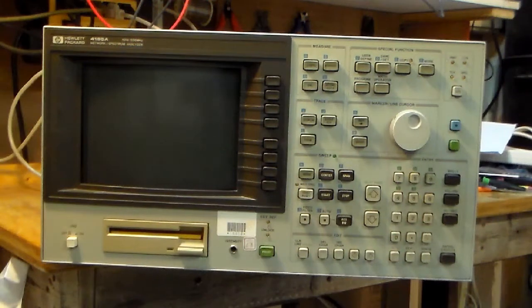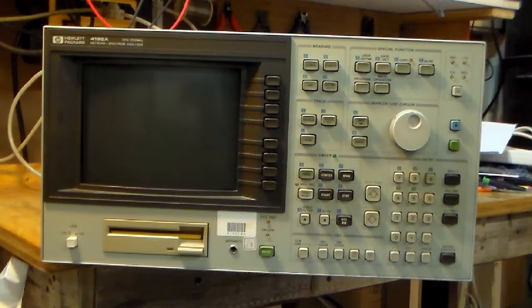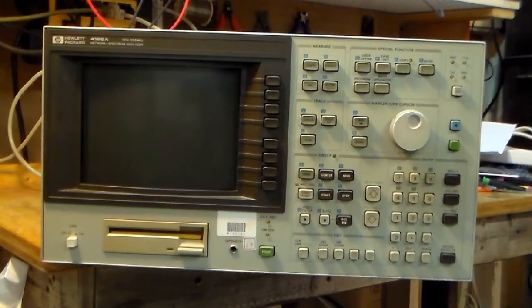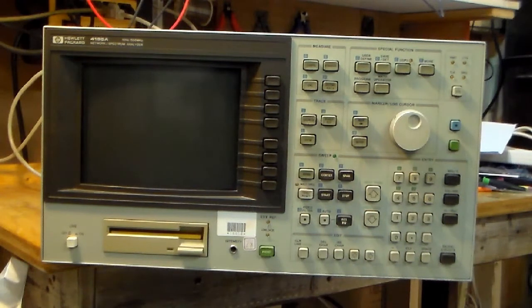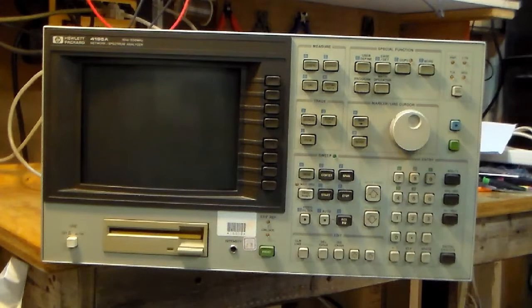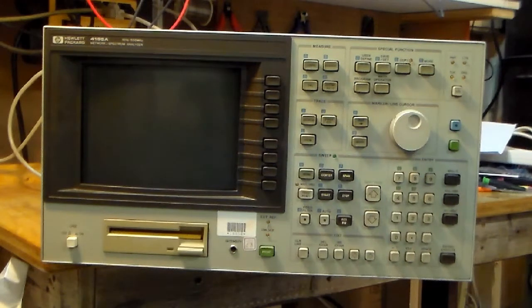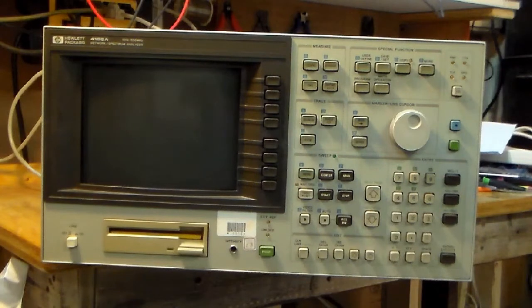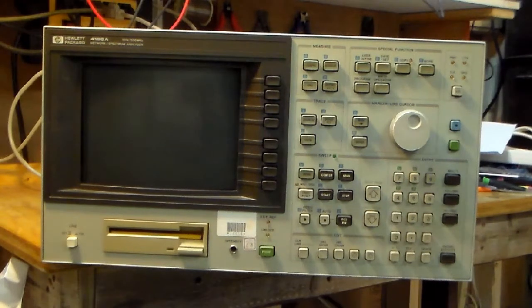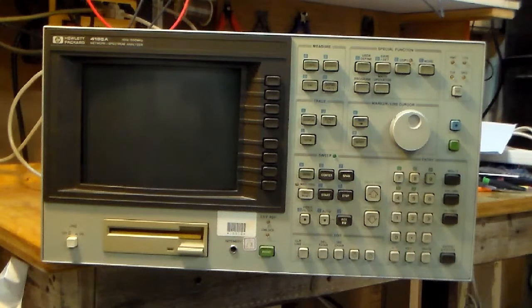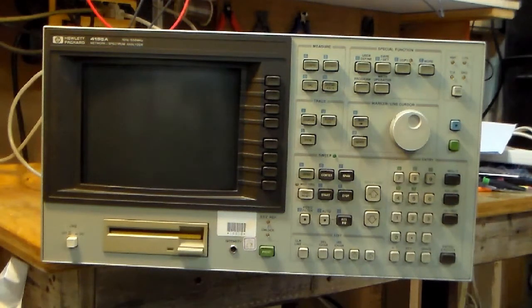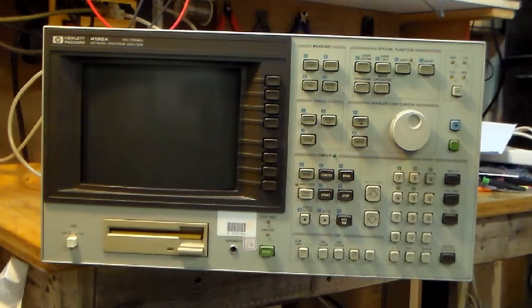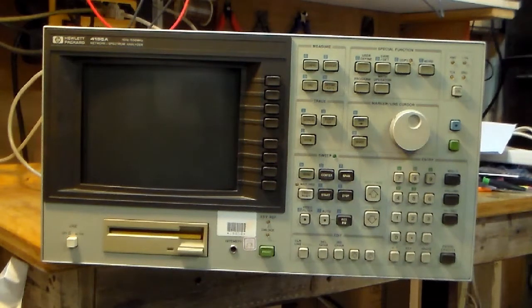Hi, in this video I will be showing my attempt at repairing this HP4195 network analyzer. I bought this as a non-functional unit. The symptoms were nothing on the display, but some LEDs turning on on the front panel. This could be caused by some power supply issues, or according to some people on the internet, the internal battery backup, which is also tied into the reset circuits, eventually goes bad and prevents the whole thing from booting.